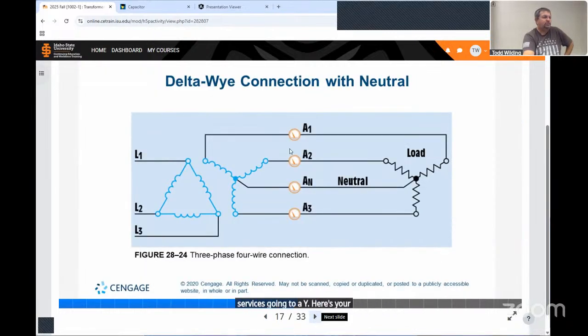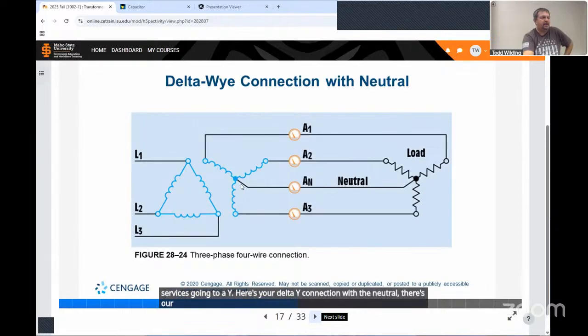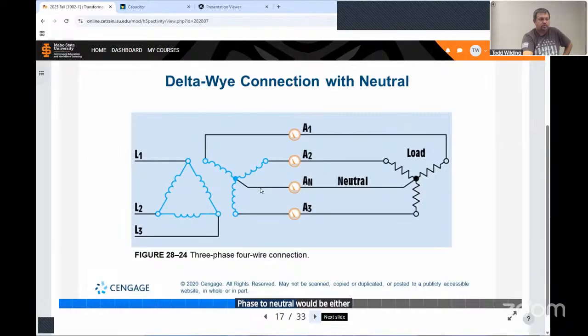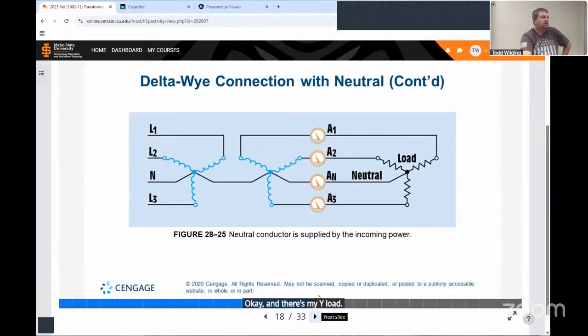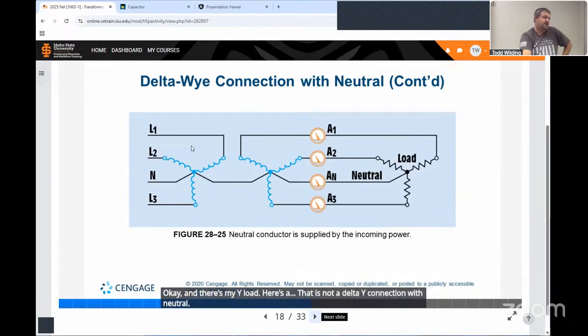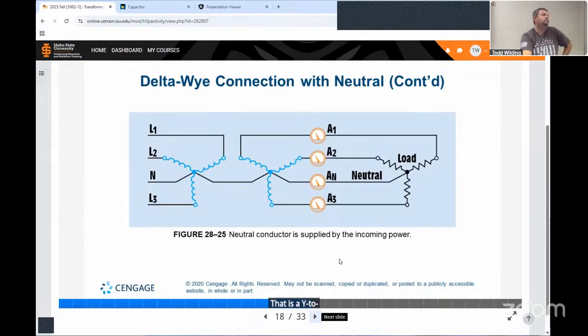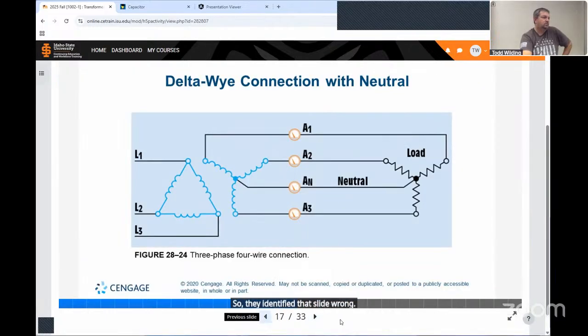Here's your delta Y connection with the neutral. There's our neutral connection right there. Phase to phase would be 208 or 480. Phase to neutral would be either 277 or 120. And there's my Y load. Here's, that is not a delta Y connection with neutral. That is a Y to Y and a Y load. So they identified that slide wrong. That'd be a YY.